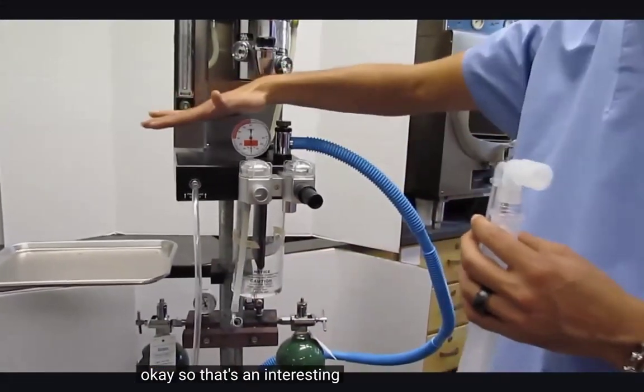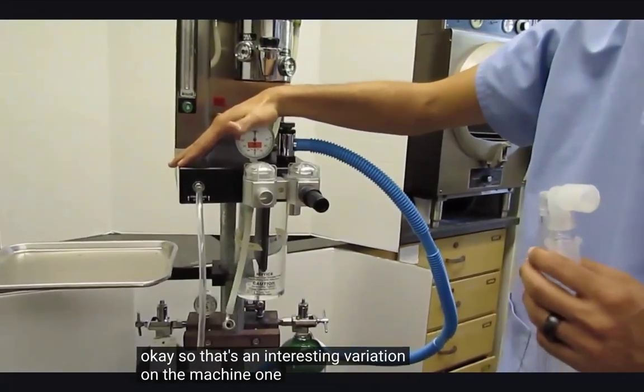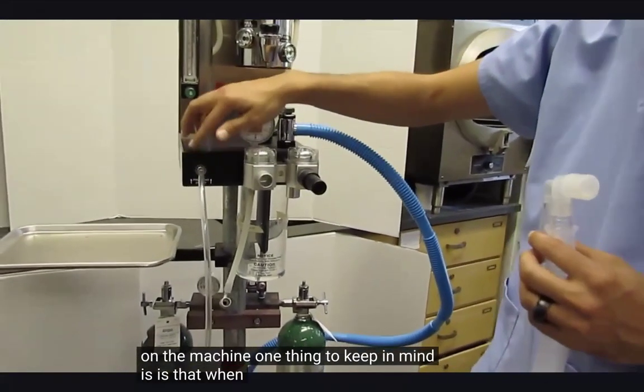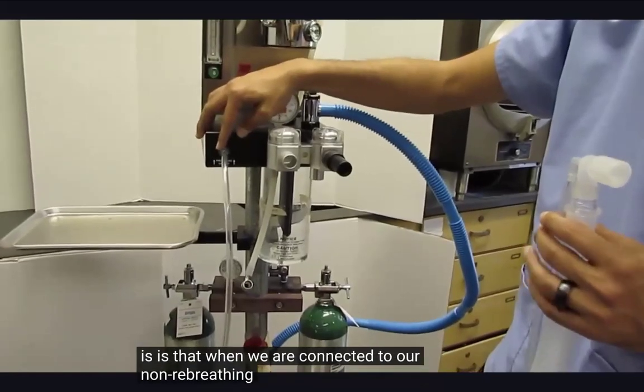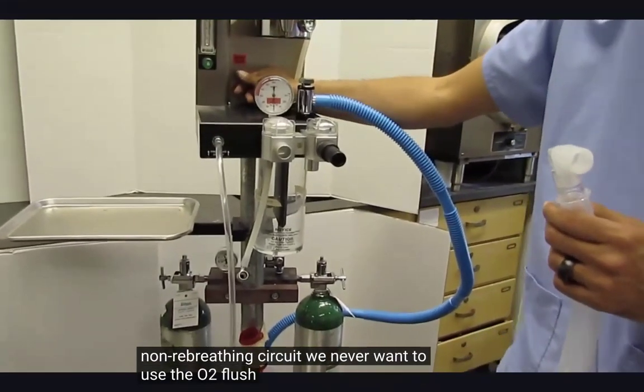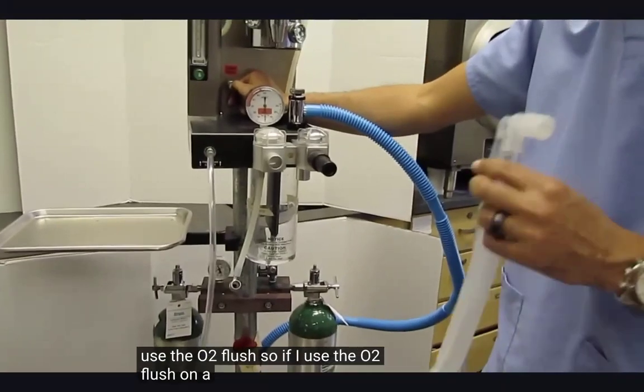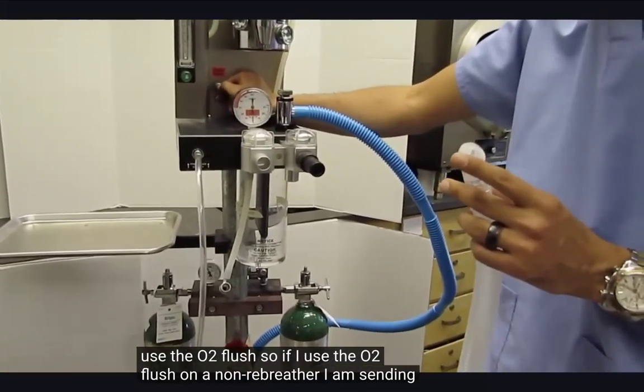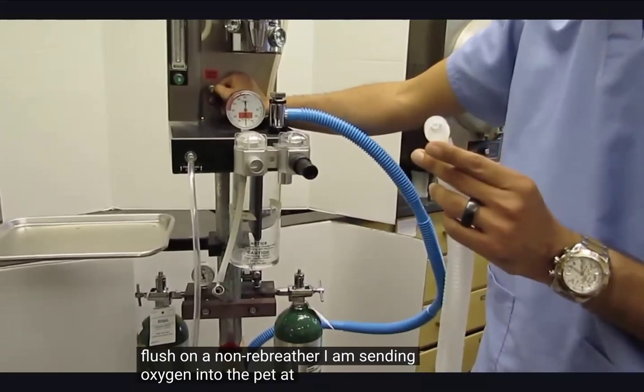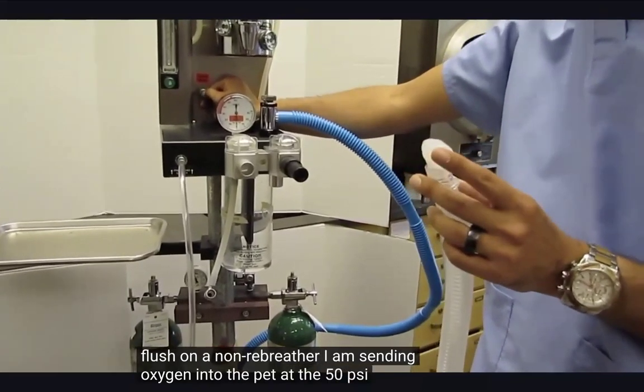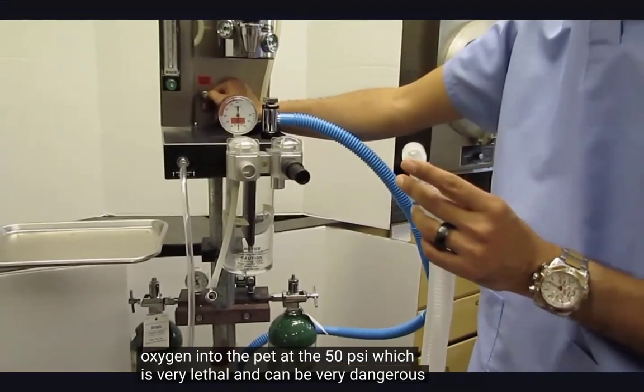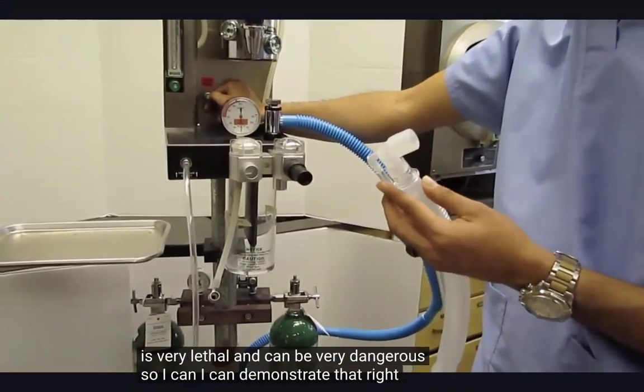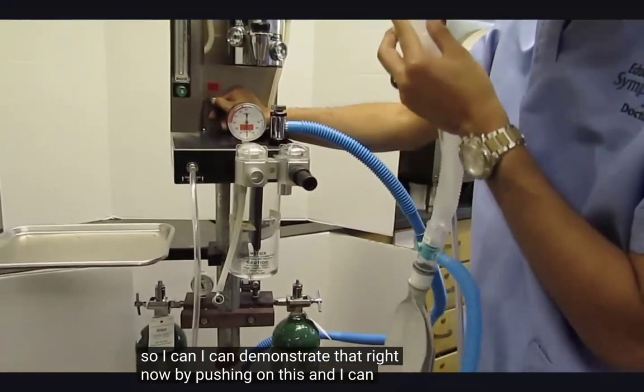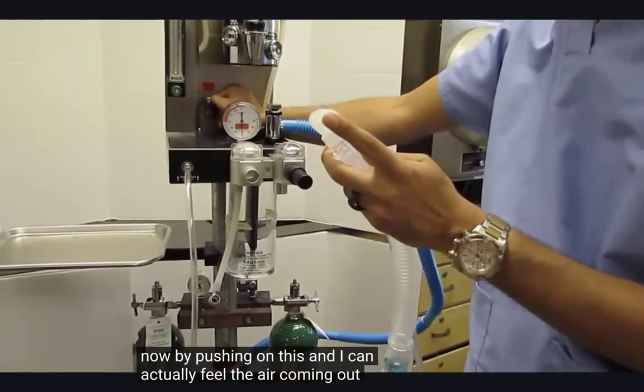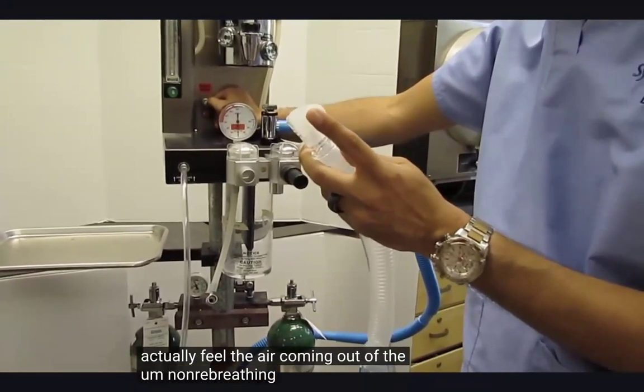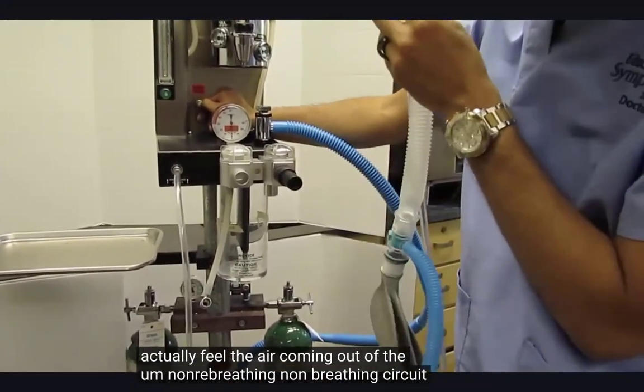So that's an interesting variation on the machine. One thing to keep in mind is that when we are connected to our non-rebreathing circuit, we never want to use the O2 flush. If I use the O2 flush on a non-rebreather, I am sending oxygen into the pet at 50 psi, which is very lethal and can be very dangerous. I can demonstrate that right now by pushing on this, and I can actually feel the air coming out of the non-rebreathing circuit. Okay?